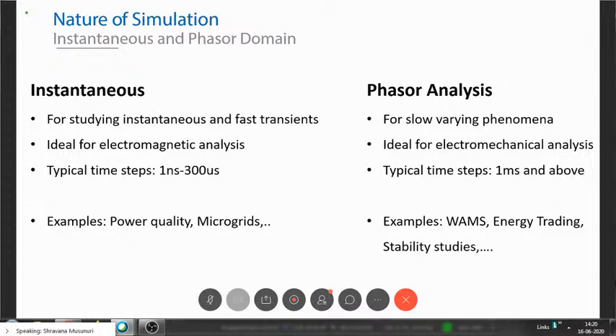Instantaneous, as the name says, means you're more interested in the instantaneous response of the system, typically fast transients, used for electromagnetic analysis. Since it's electromagnetic, we look at very high frequencies, so the recommended time step is from 1 nanosecond to 300 microseconds, depending on how fast the transients you're interested in are. Best examples are power quality applications and microgrids.